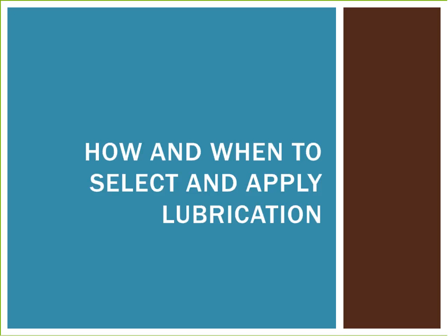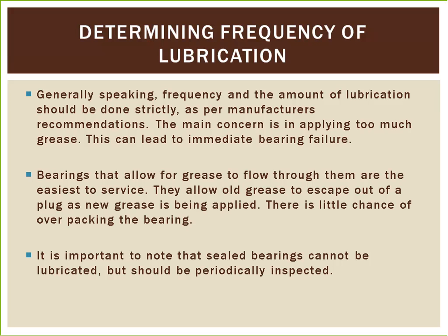Next, we will review how and when to select and apply lubrication. Generally speaking, frequency and the amount of lubrication should be done strictly per the manufacturer's recommendations. The main concern is in applying too much grease. This can lead to immediate bearing failure. Bearings that allow for grease to flow through them are the easiest to service. They allow old grease to escape out of a plug as new grease is being applied. There is little chance of overpacking the bearing. It is important to note, though, that sealed bearings cannot be lubricated, but should be periodically inspected.